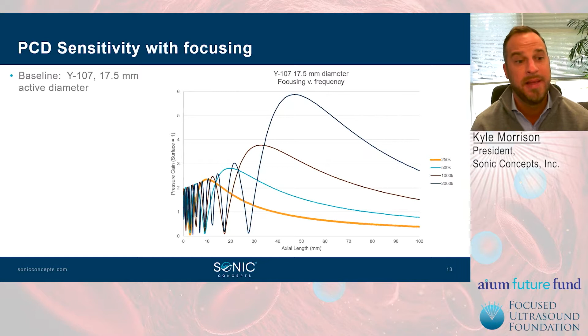So focused PCDs are very difficult to calibrate within a reasonable uncertainty. This spatial resolution across the frequency spectrum is very difficult to quantify. Normally a needle hydrophone, for context, is calibrated at a point in the far field since the spatial resolution isn't an issue. The focused PCD geometric focus cannot be assumed to be in phase in this case.